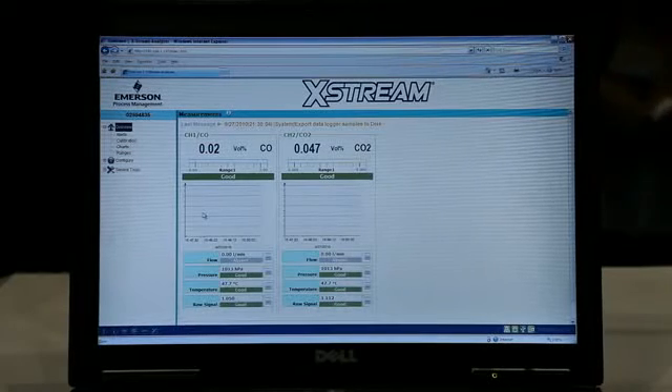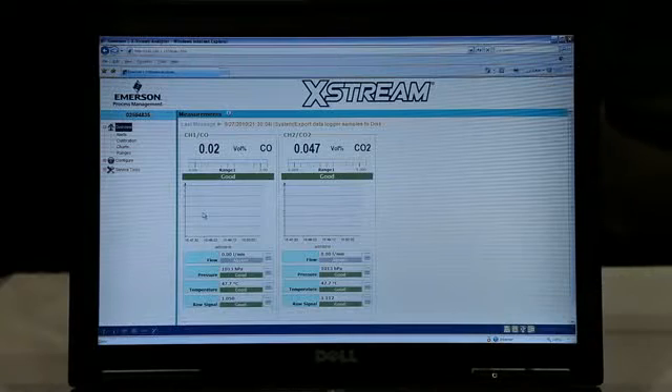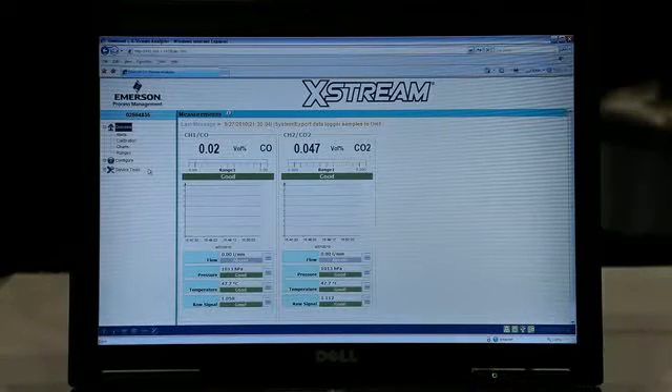Utilizing a standard web browser, we're communicating with the X-STREAM XE process gas analyzer. Here we have the overview screen. As you can see, we have drop-down menus here to configure and perform service remotely at any time from anywhere.